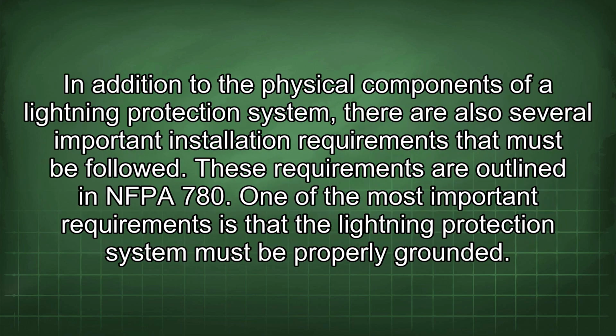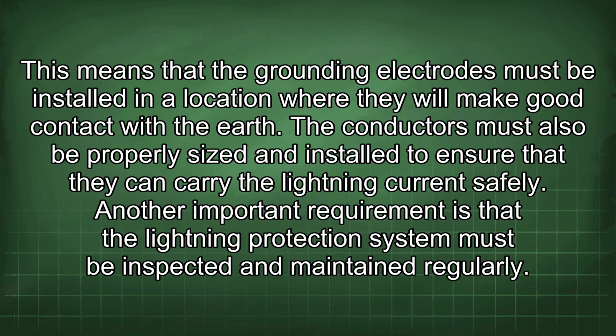In addition to the physical components of a lightning protection system, there are also several important installation requirements that must be followed. These requirements are outlined in NFPA 780. One of the most important requirements is that the lightning protection system must be properly grounded. This means that the grounding electrodes must be installed in a location where they will make good contact with the earth. The conductors must also be properly sized and installed to ensure that they can carry the lightning current safely.